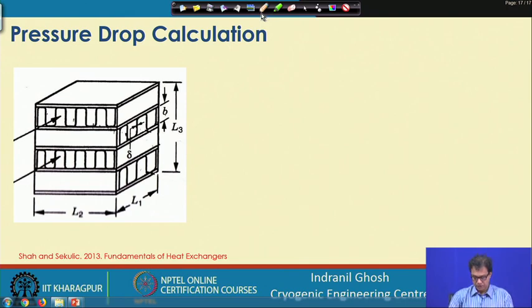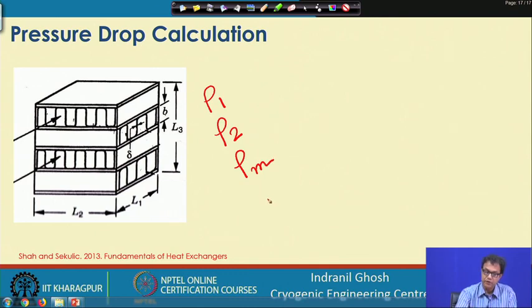First of all, if we look into our pressure drop expression, we have Ke, Kc, then sigma, then we have the different densities rho 1, rho 2, and P1 is already given. So, in our hand we have all the parameters known to us, and we have to calculate them one by one. We have to estimate rho 1, rho 2, then rho m, then we need to look at G, the mass velocity, then Ke, then Kc and sigma.